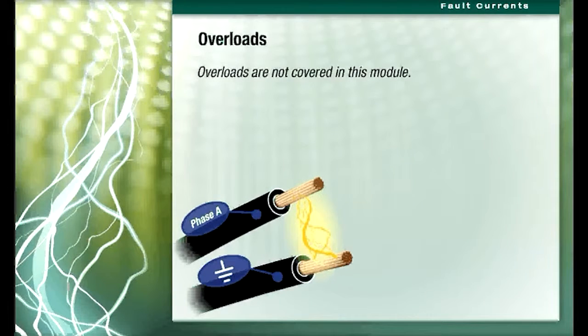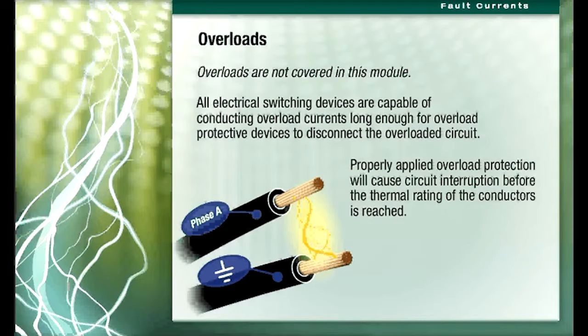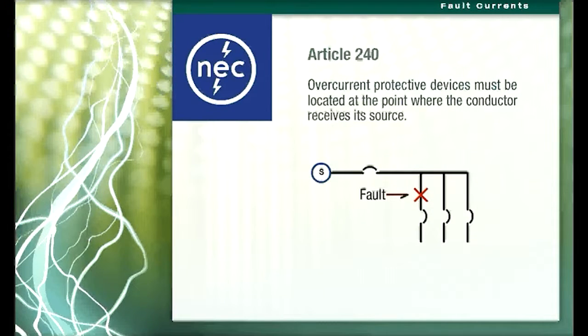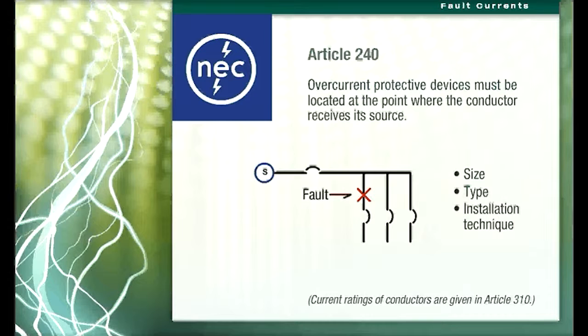Overloads will be ignored in this discussion because all electrical switching devices are capable of conducting overload currents long enough for overload protective devices to disconnect the overloaded circuit. Properly applied overload protection will cause circuit interruption before the thermal rating of the conductors is reached. NEC Article 240 establishes the criteria for the selection and location of overcurrent protective devices. In essence, the code requires that the overcurrent protection be located at the point where the conductor receives its source.